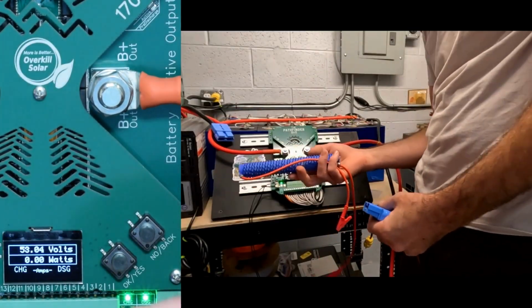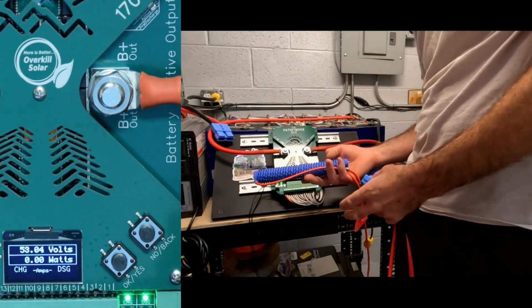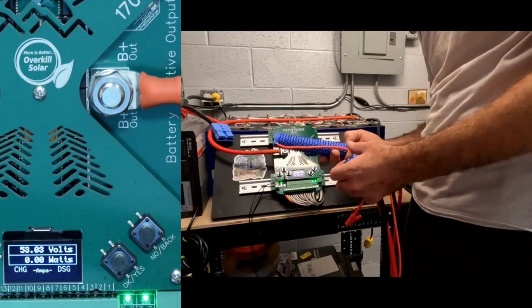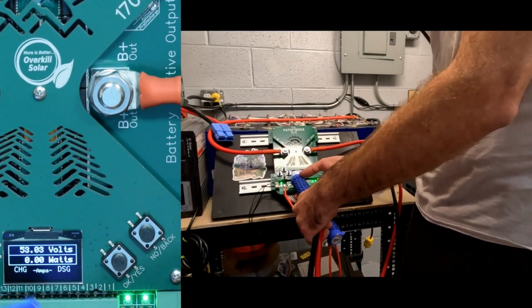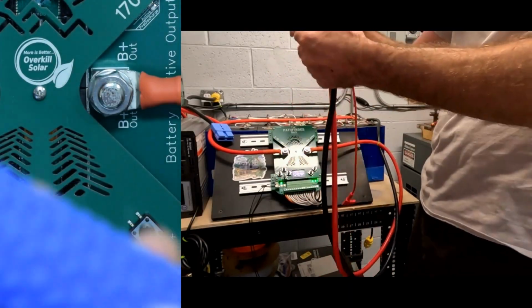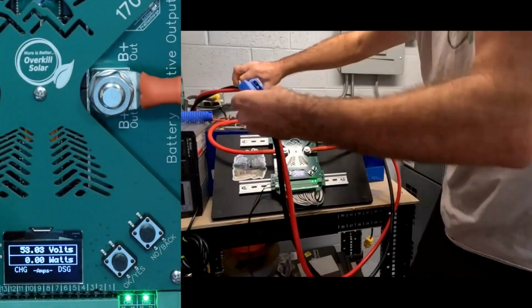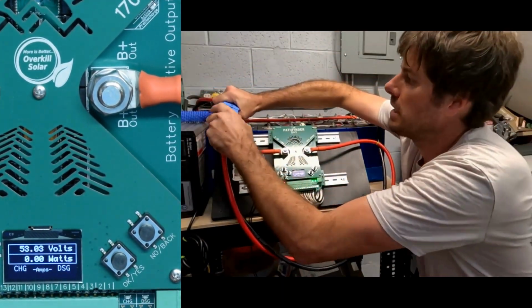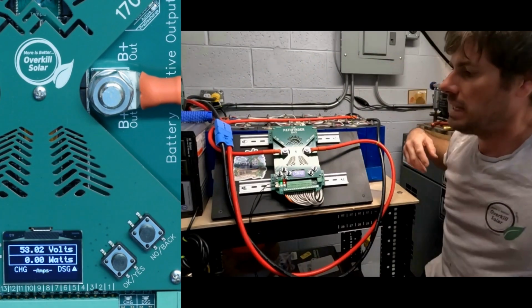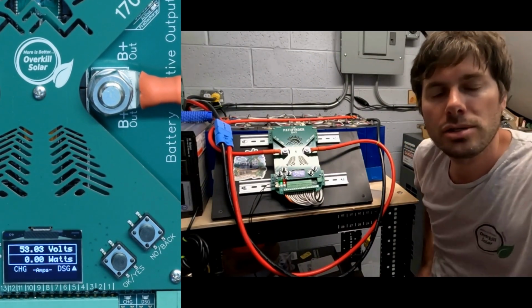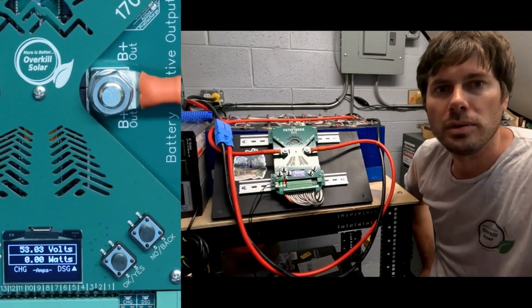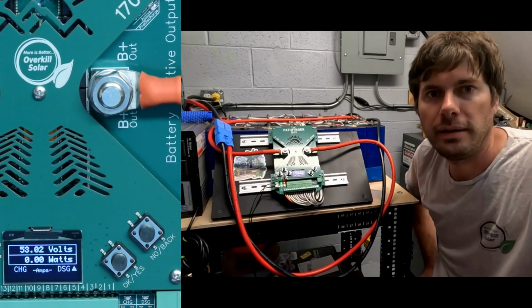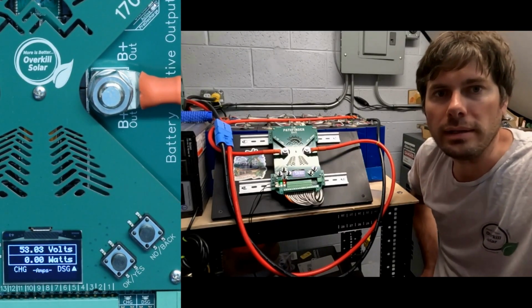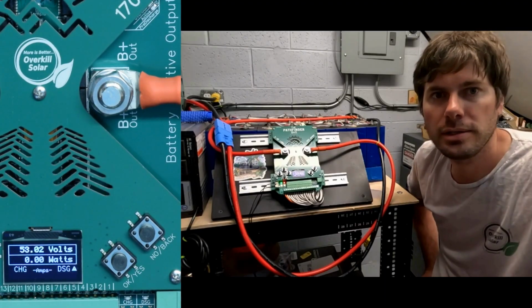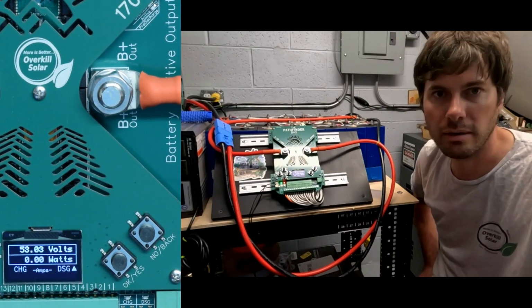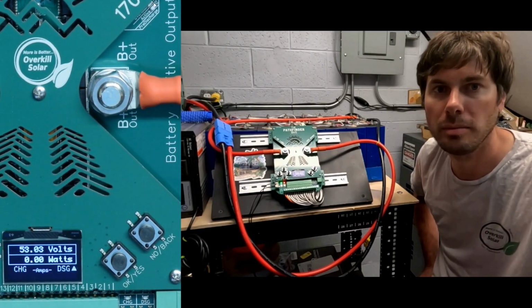This is a 0.73 ohm load resistor. I'm going to connect that right to the terminals on the back of the inverter. Alright, so we'll do the same demonstration again. And then when the pre-charge circuit tries to start, we'll see that there's an overload indicated. That means that there's too much load on the system for the pre-charge circuit to charge it up, and you'll need to remove some of the heavy loads in order to power up the system.